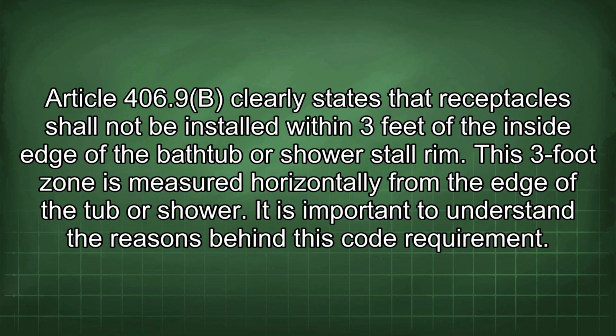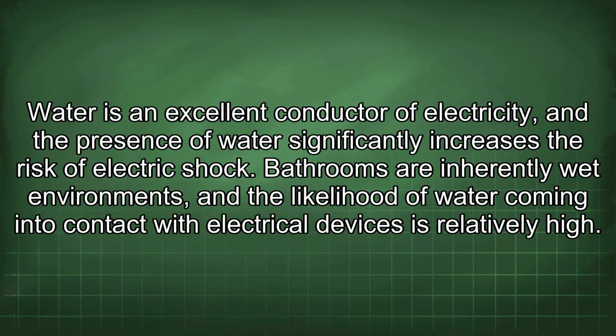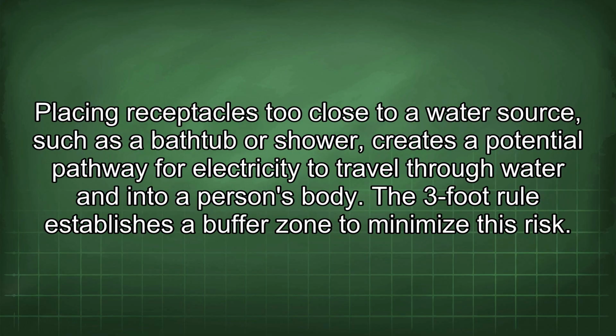It is important to understand the reasons behind this code requirement. Water is an excellent conductor of electricity, and the presence of water significantly increases the risk of electric shock. Bathrooms are inherently wet environments, and the likelihood of water coming into contact with electrical devices is relatively high. Placing receptacles too close to a water source, such as a bathtub or shower, creates a potential pathway for electricity to travel through water and into a person's body. The 3-foot rule establishes a buffer zone to minimize this risk.